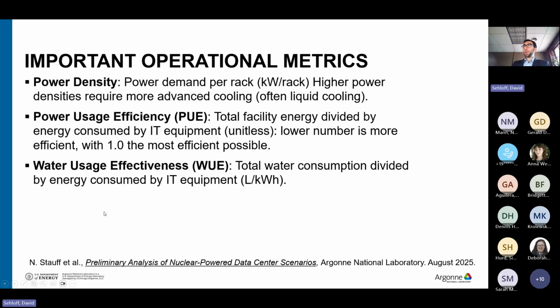So a few operational metrics to keep in mind: power density, how much demand is needed per rack—we need better cooling if there's higher power density. The power usage efficiency is a very common metric, where a lower number is better, with 1.0 being the most efficient we can get. The water usage effectiveness is how much water is consumed compared to the energy consumed by the IT equipment.